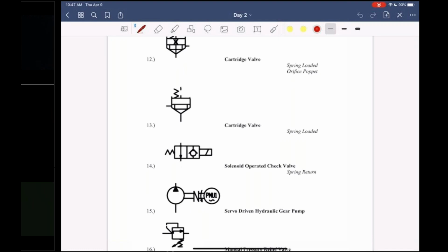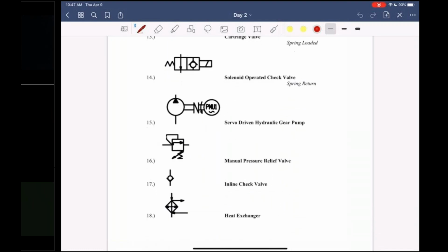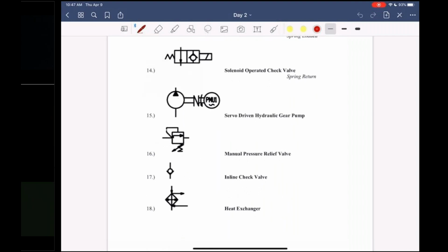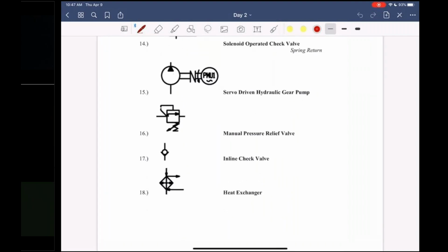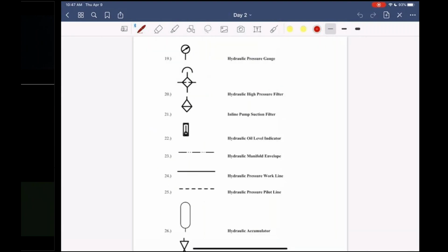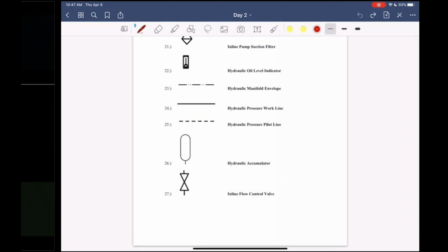And then you have a solenoid operated check valve, spring return, servo driven hydraulic gear pump, manual pressure release valve, inline check valve, and a heat exchanger. Hydraulic pressure gauge, hydraulic high pressure filter, inline suction filter, hydraulic oil level. This is a manifold envelope. Then you have your hydraulic pressure work line, hydraulic pressure pilot line, hydraulic accumulator, inline flow control valve.